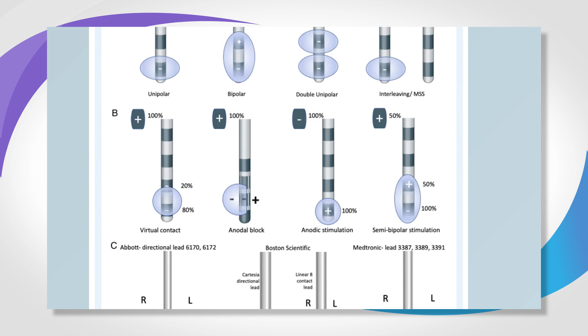On the bottom here, it's just important for you to know how the electrodes are actually numbered. On the Abbott device, they're numbered 1. The two middle levels are segmented into thirds, and they're labeled 2 ABC, 3 ABC, and the top contact is a single contact labeled number 4. On the other side, if you have a second battery, the numbering is 9, 10 ABC, 11 ABC, and 12. On the Boston Scientific device, they're numbered 1, 2, 3, 4, 5, 6, 7, 8, and then 9 through 16, on the segmented lead and also on the 8 contact linear lead. And the older Medtronic device electrodes are numbered 0, 1, 2, 3, and then 8, 9, 10, 11.